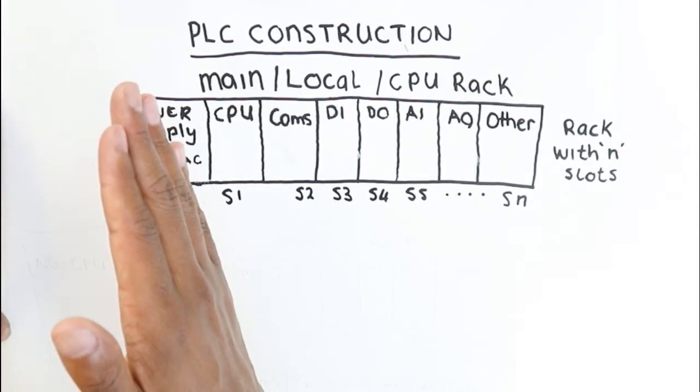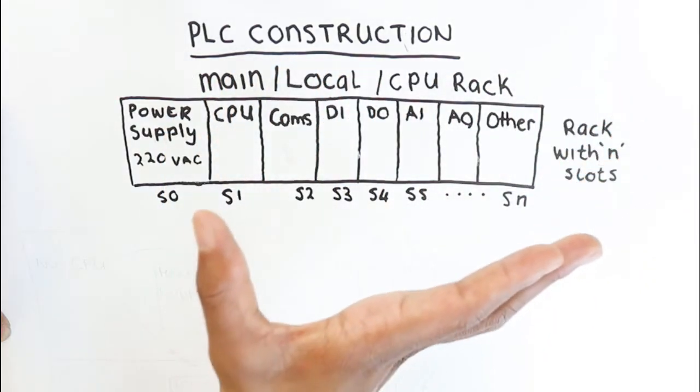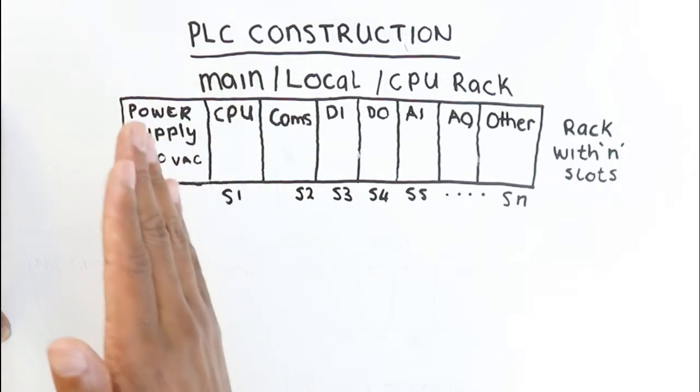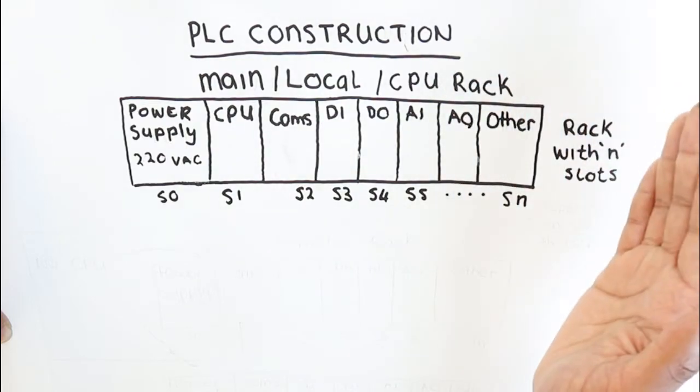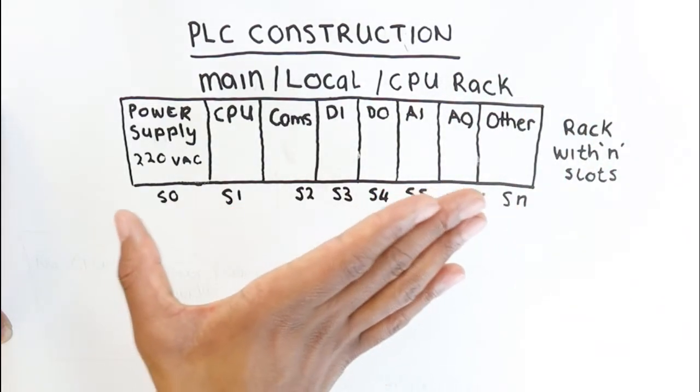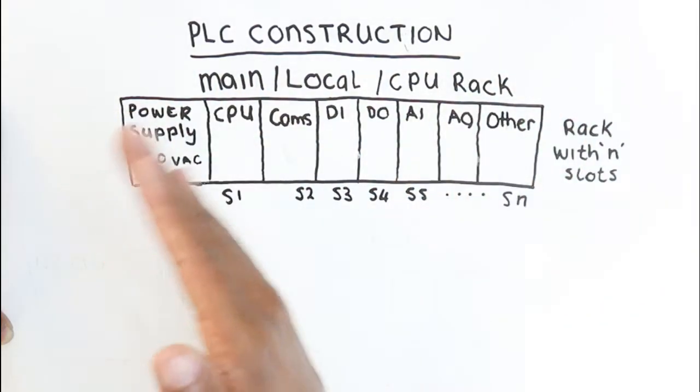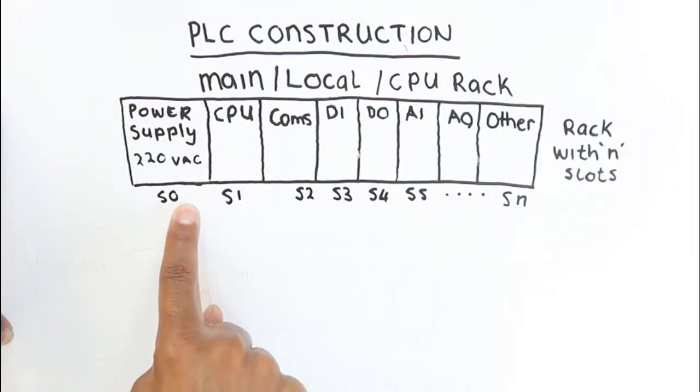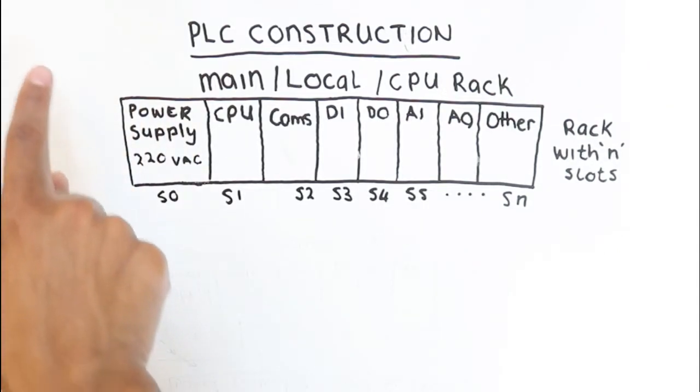Now I must emphasize this: the order in which you can have the cards on the rack may change with different manufacturers. Some manufacturers are strict in terms of where you put particular cards on a PLC rack. Some manufacturers do not have specific rules of where you can place the cards, but I've just gone with a general example or a usual industrial convention of how you would set up your PLC rack.